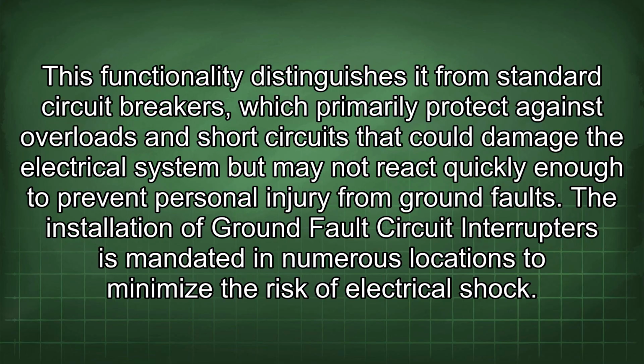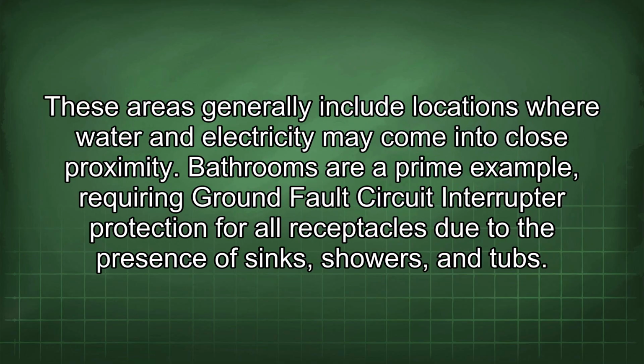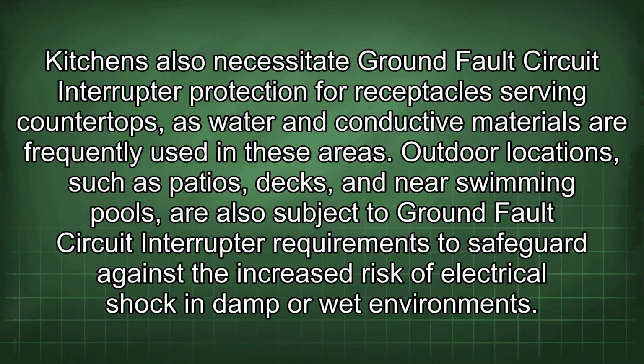The installation of ground fault circuit interrupters is mandated in numerous locations to minimize the risk of electrical shock. These areas generally include locations where water and electricity may come into close proximity. Bathrooms are a prime example, requiring ground fault circuit interrupter protection for all receptacles due to the presence of sinks, showers, and tubs. Kitchens also necessitate ground fault circuit interrupter protection for receptacles serving countertops, as water and conductive materials are frequently used in these areas.